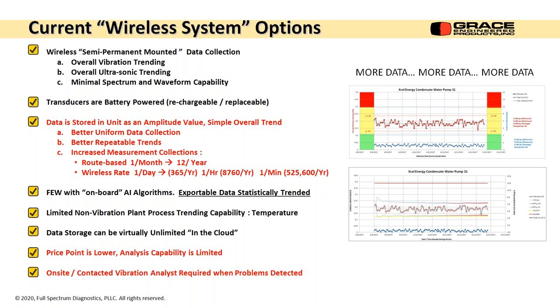With current wireless system options, a lot of them, the first one, go to semi-permanent mounted data collection to get some of this capability. The transducer is battery powered in some cases, and sometimes they're wired in as well. But here's the thing that makes it really valuable. If you do route-based vibration analysis, you're only getting about 12 measurements a year at any given point on your machine. 12 measurements is tiny. I have an example here to the right. This was 4 days' worth of data, one data point per hour, so about 94 measurements. Because it's magnet mounted, we get better uniform data collection. Nobody's walking around and touching a different point.